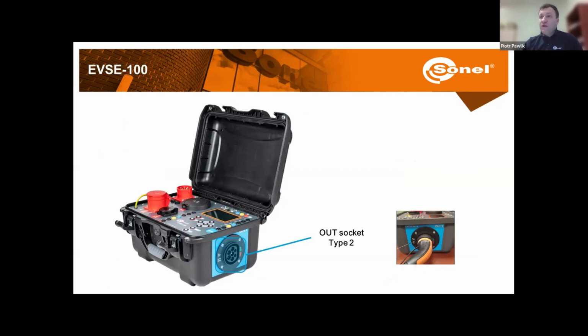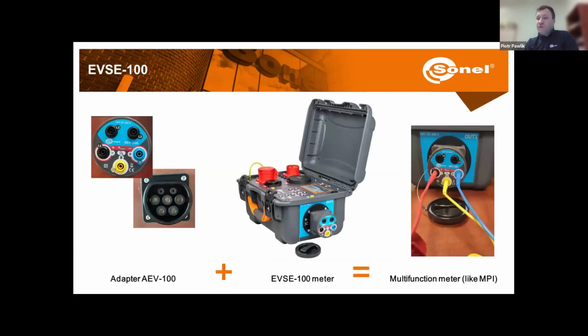And furthermore, as standard, this meter will come with an adapter called AEV100. So when we put it into the out socket and connect the test leads, like you can see here in the picture, it is going to work similarly to a multifunction meter, which can check different parameters of even a regular electrical installation.